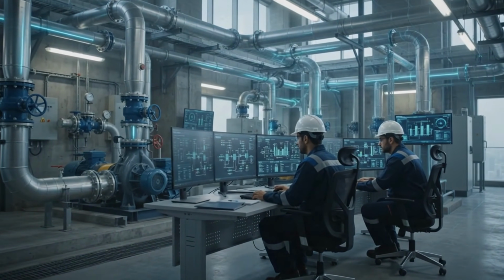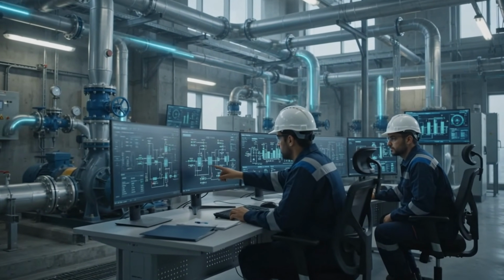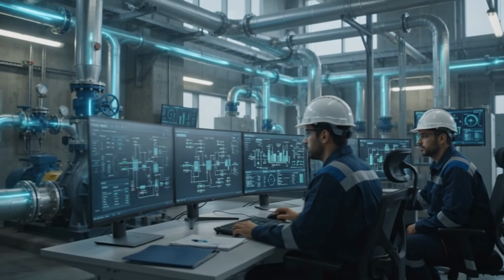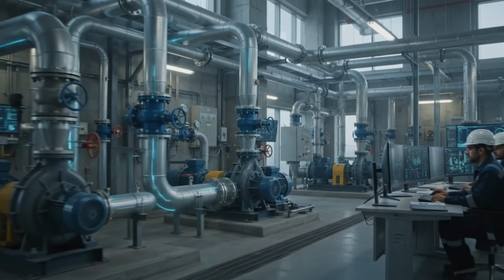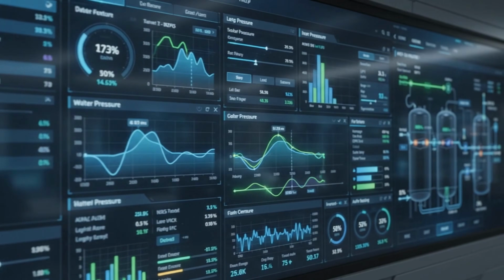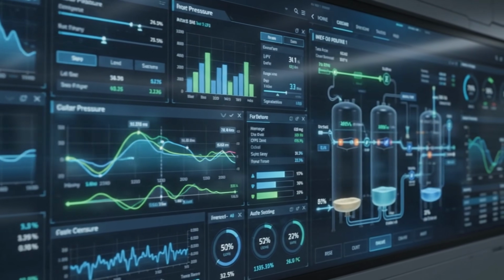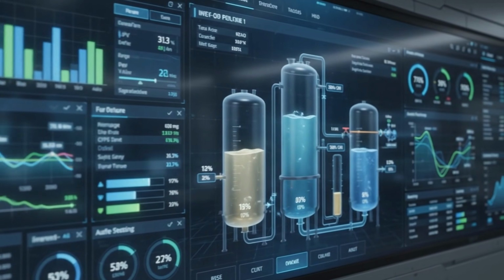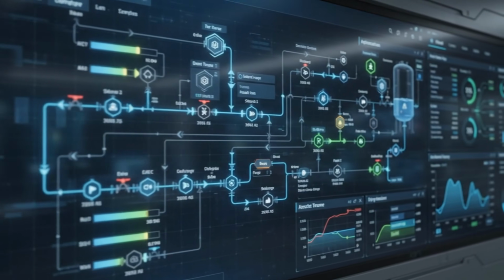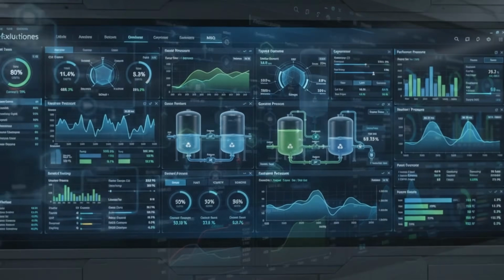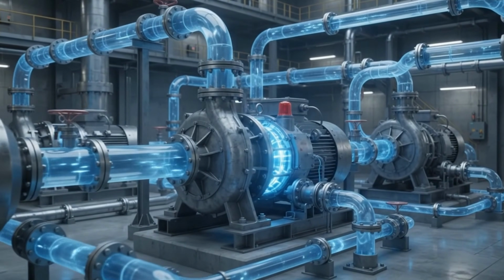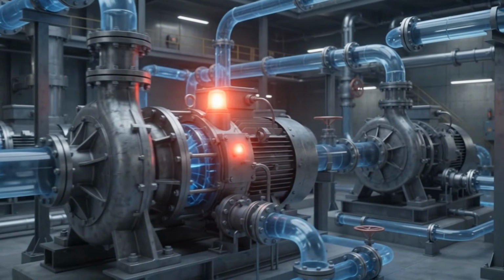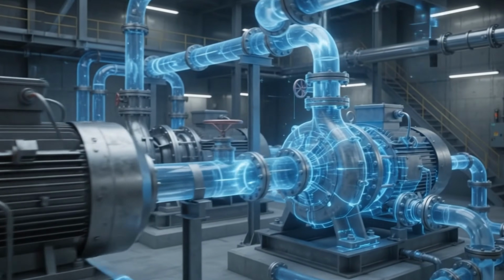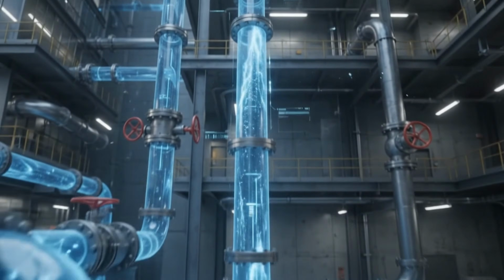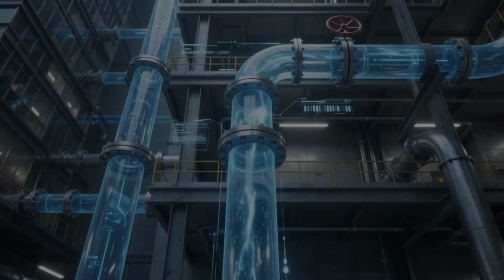Real-time visibility: flow rates, pressure readings, tank levels, and pump status, all displayed on centralized monitoring screens. From a central command hub, a team of building engineers can see the status of every pump, every tank, and every valve in the tower, and respond to anomalies within seconds. Every pump in this system has a backup. When a primary pump fails, the backup takes over within milliseconds, because in a building this size, there is no acceptable downtime.